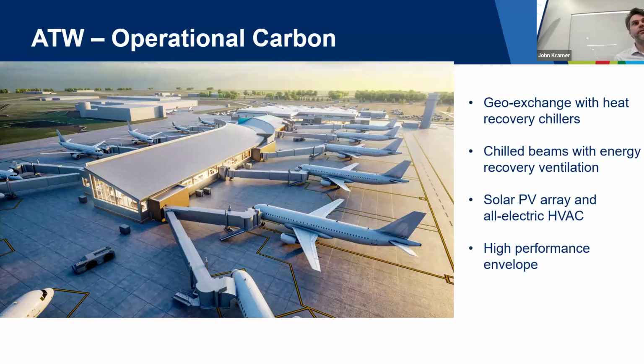And then heat recovery chillers are nice because they're all electric. They couple well with geo-exchange loops, and they can simultaneously heat and cool. So while you're heating, say, the perimeter of the building, the interior has a high people load putting off enough heat that you're always in cooling at some part of the year. You can extract heat from the refrigerant of that heat recovery chiller and use it to heat the perimeter of the building. So it's a great efficiency measure. You're taking something that would have been wasted, recovering it and using it for the building, and lowering your energy use intensity, or EUI. So it's a really great efficiency measure.